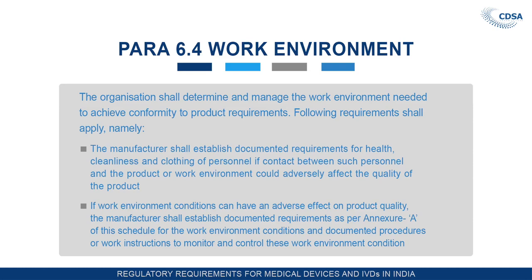Namely, the manufacturer shall establish documented requirements for health, cleanliness and clothing of all personnel, if contact between such personnel and the product or work environment could adversely affect the quality of the product. That means, in simple language, if an operation requires that the personnel shall wear gloves and full body suit, that's part of it. If they require to wash their hands and feet before entering an area, that forms part of the environment.